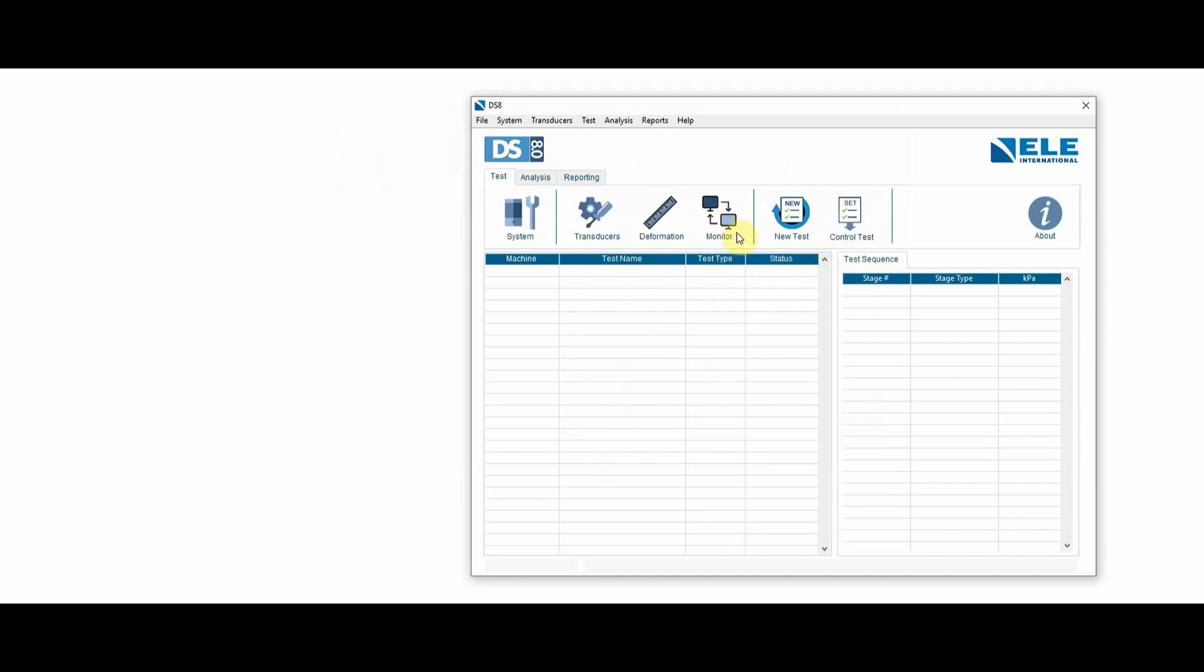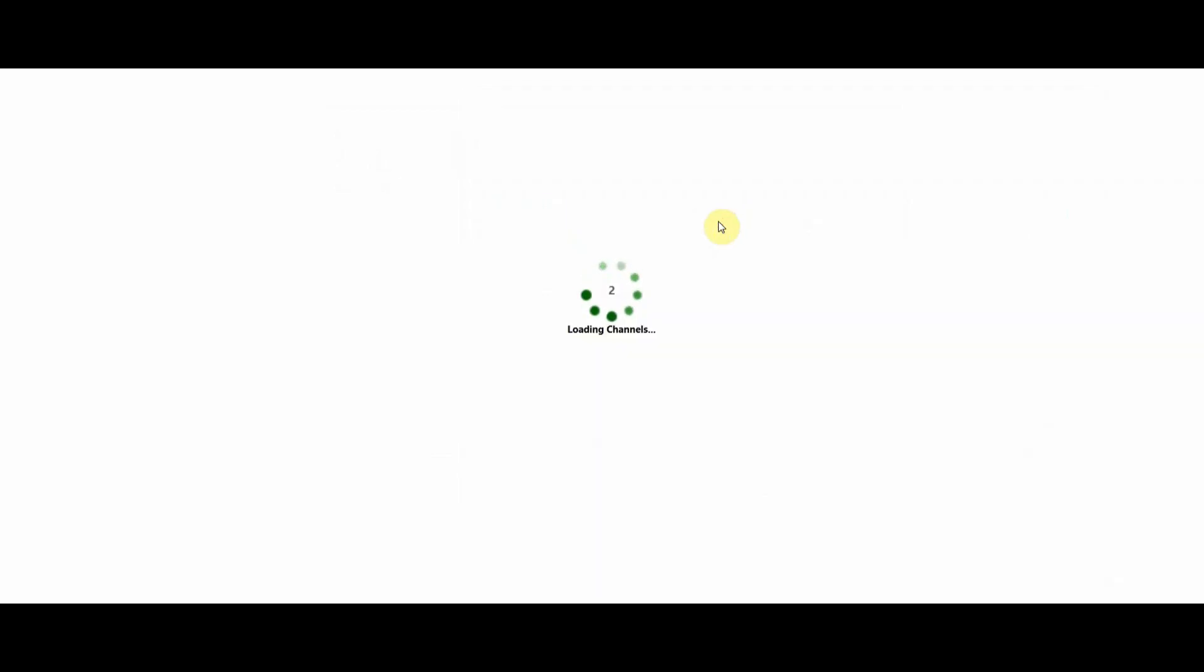Furthermore, what I can do is click on the monitor option, and this will take me to a screen where I can check my transducer. So if I add the transducer for the force, it'll display basically a live reading of it. If I squeeze it with my hand, I should be able to get a reading out of it. So we know that that is correct.